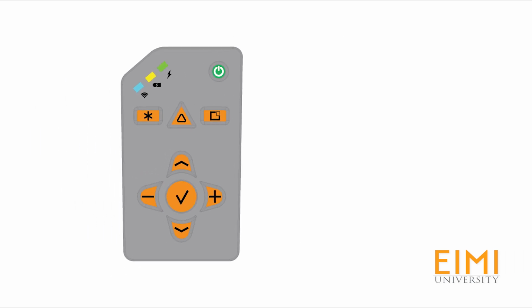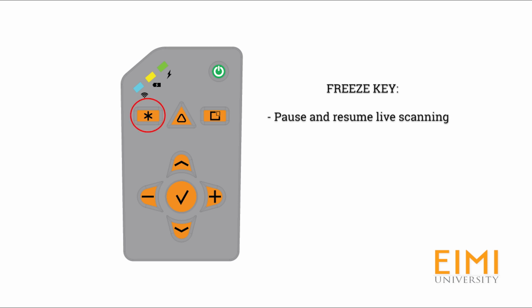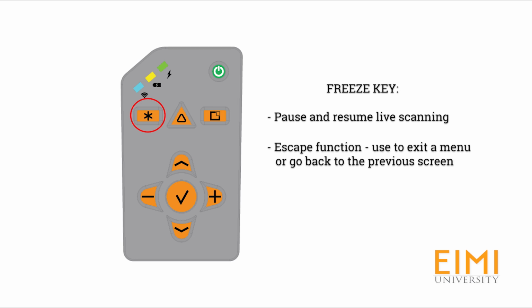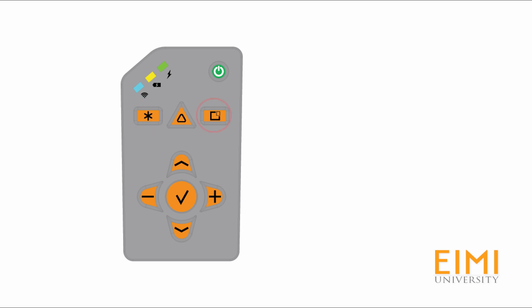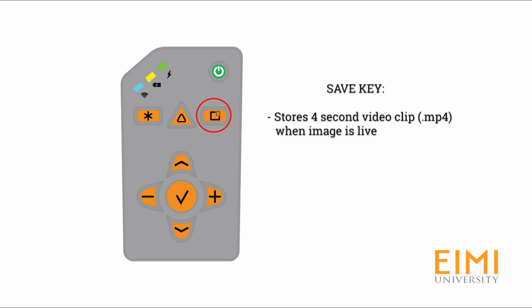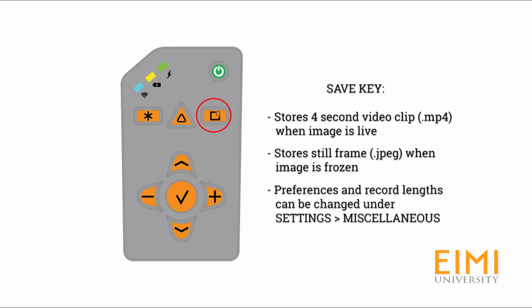The freeze key is represented by a snowflake icon. It acts to pause and reactivate the live image. Its other important function is as a back or escape key. Use it to exit menus or return to the previous screen. The disk icon is the save key. By default, this key records a video loop of 4 seconds when live or a still frame when freeze is activated. The function and record length of this button can be changed under the Settings and Miscellaneous menu.